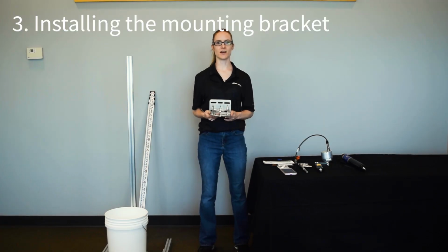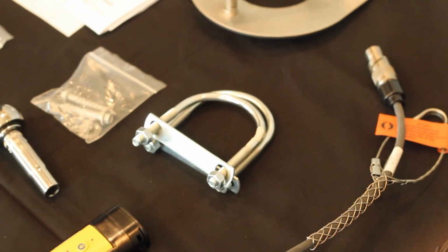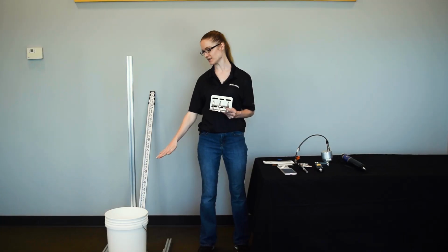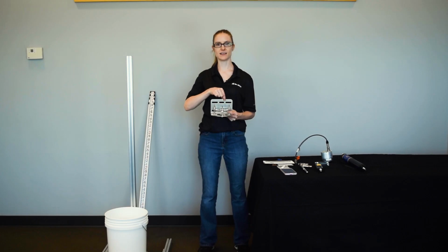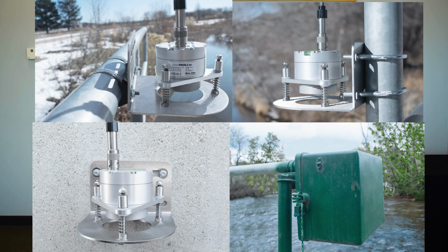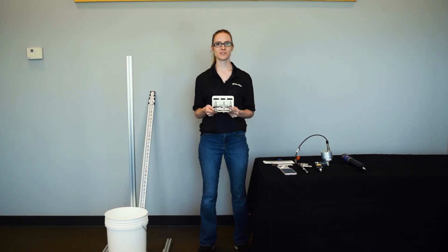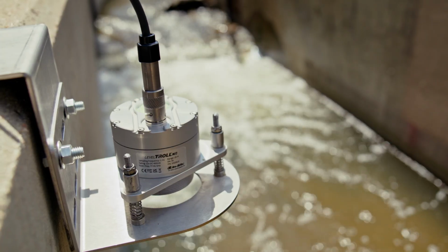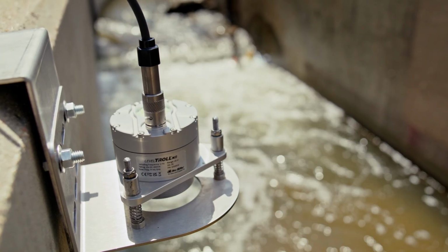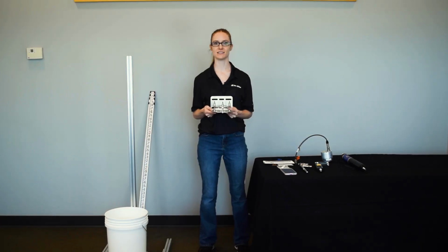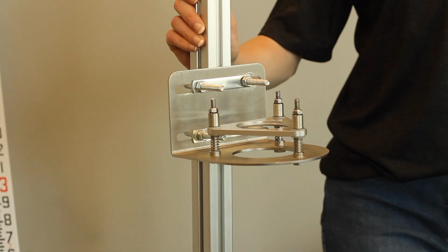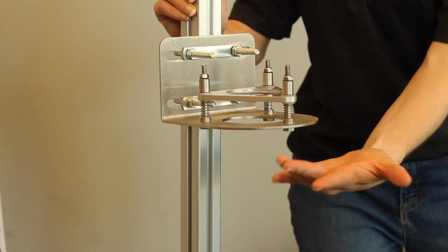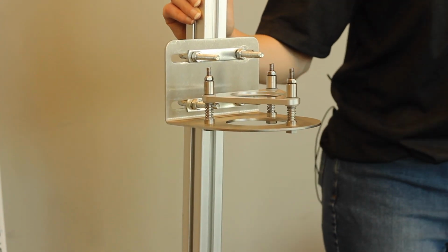Now, it's time to pull out the mounting bracket. For the sake of this video, I'm just going to be using these U-bolts I picked up at the hardware store to secure my instrument over this bucket of water. The 3/8" slots on the bracket support a variety of mounting styles with U-bolts, band straps, concrete mounting screws, or inside a box or enclosure. The most important thing is to make sure the mounting bracket will be secure, solid, and level in the full range of conditions expected for the entire deployment, and to make sure there is a clear area under the instrument that is free from metal and other interferences.